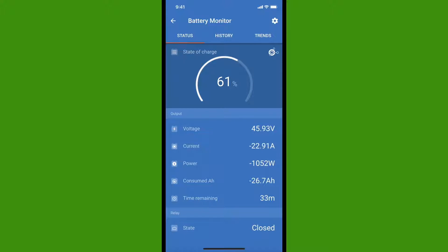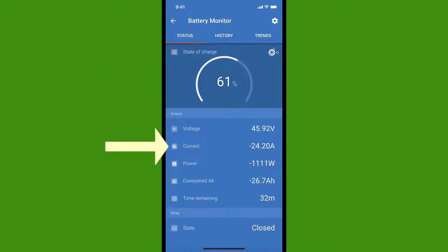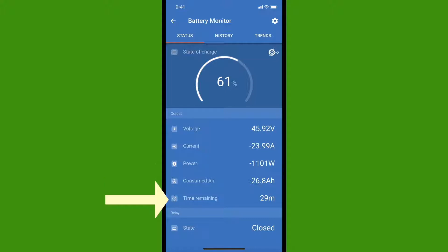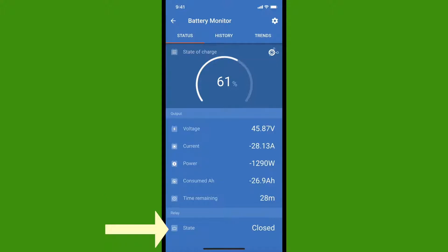Starting at the top, we have the state of charge, the voltage, the current measured in amps, the power measured in watts, the consumed amp hours, or how many amp hours you've used since the last time the battery was at a full charge, and the time remaining before the battery is completely drained. Down at the bottom is a relay, which I'm not using, but it could be used to start a generator or control another secondary load that only comes on when your battery is fully charged, allowing you to dump that excess power somewhere.